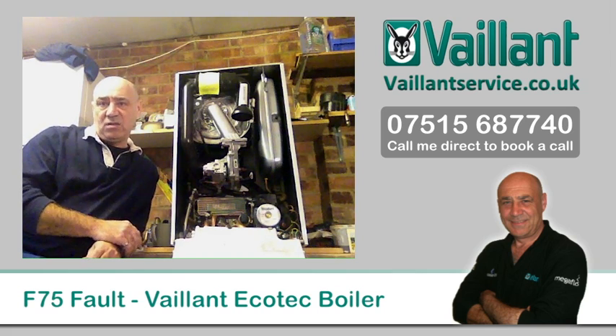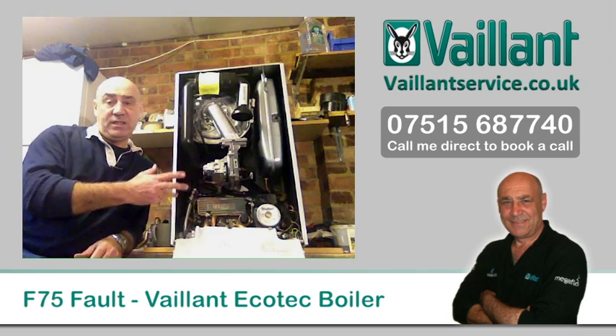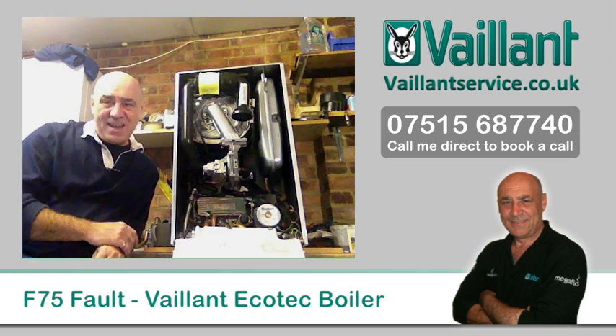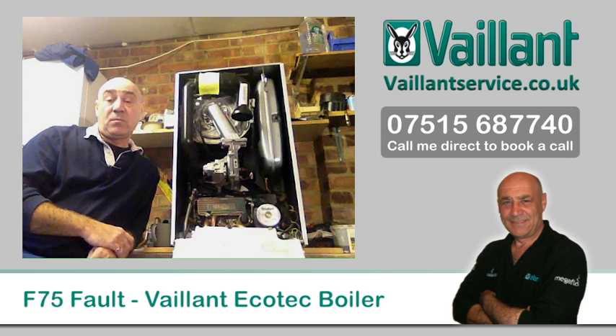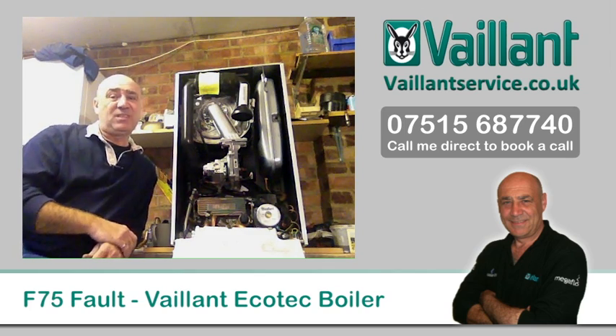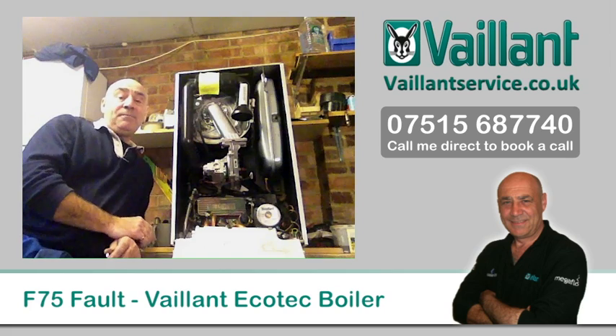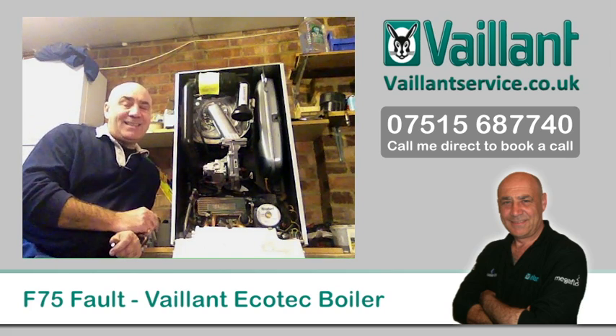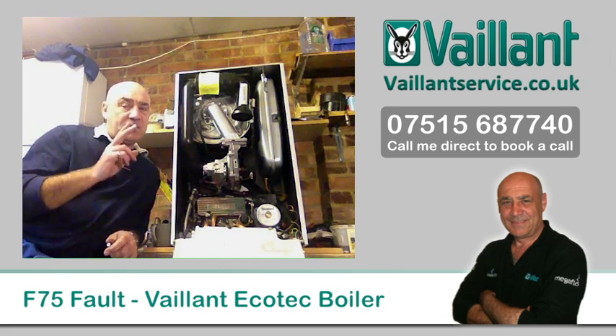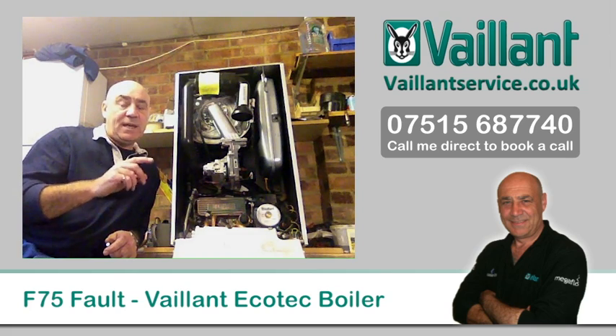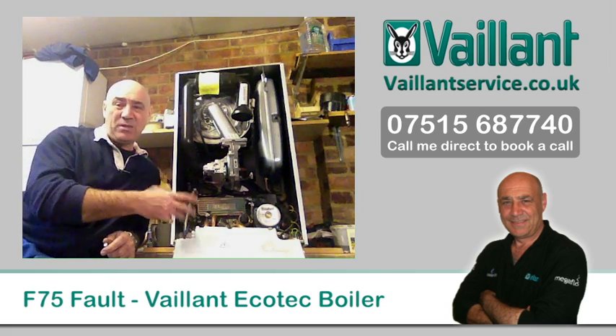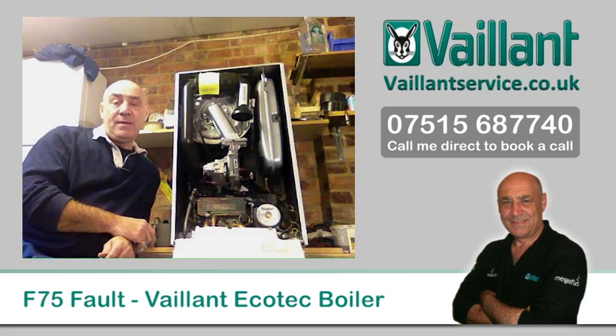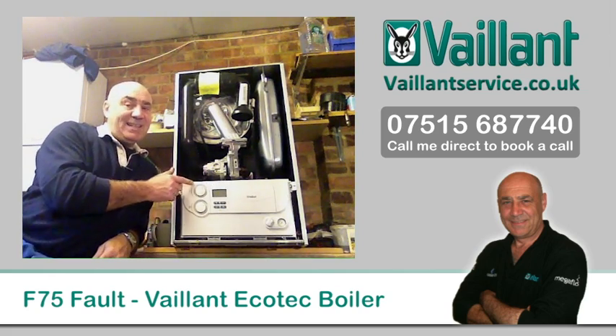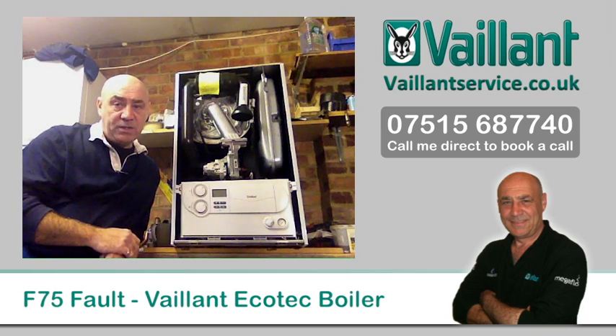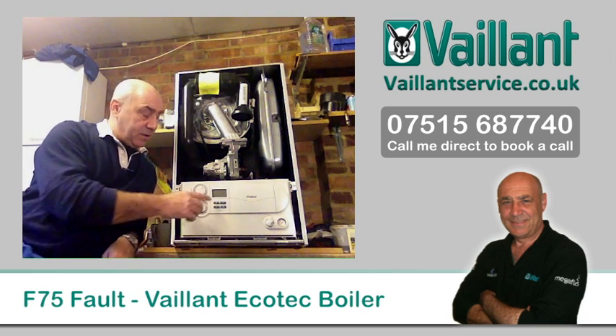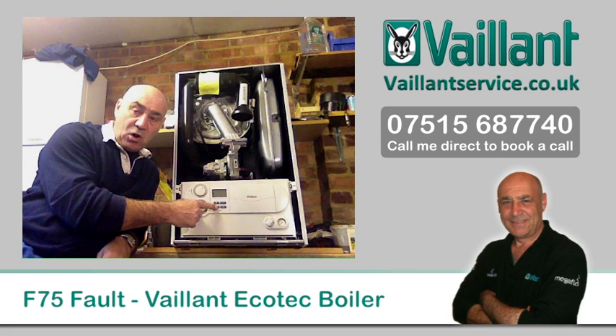So the boiler has lots and lots of safety devices built in, not just the Ecotec but all boilers, to prevent that occurring, or to stop people putting the boiler on with no water in it. This boiler has an electronic sensor, and this sensor does two things. It constantly monitors the actual water pressure inside the boiler system itself. You can see this quite easily, without using the worst pressure gauge in the world, simply by pushing the minus button here on the display.